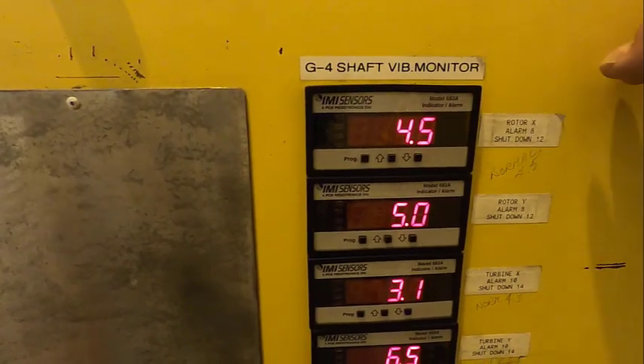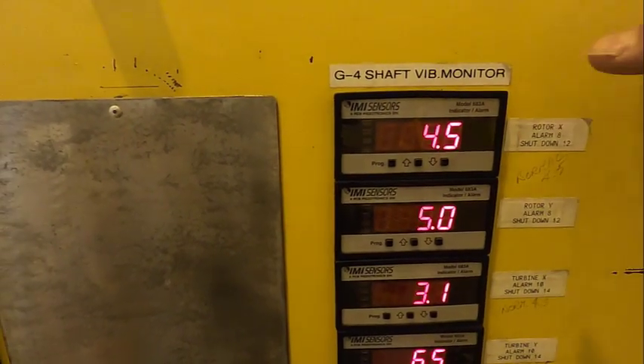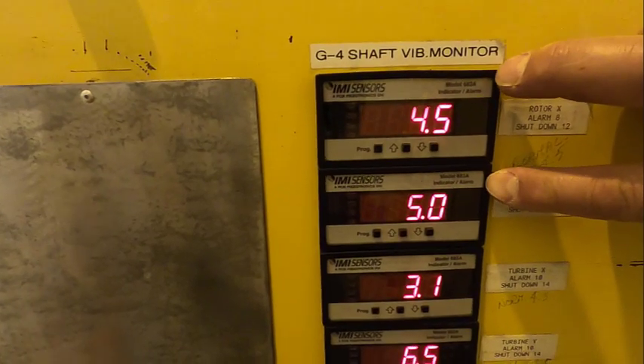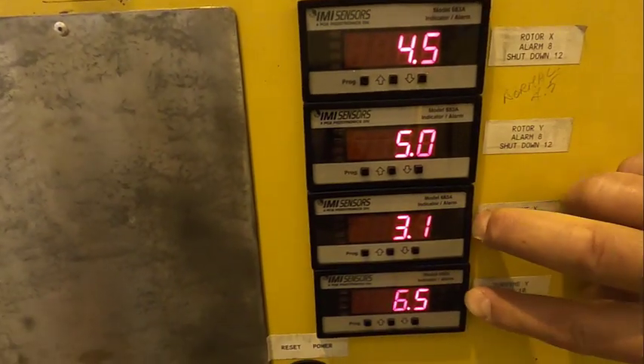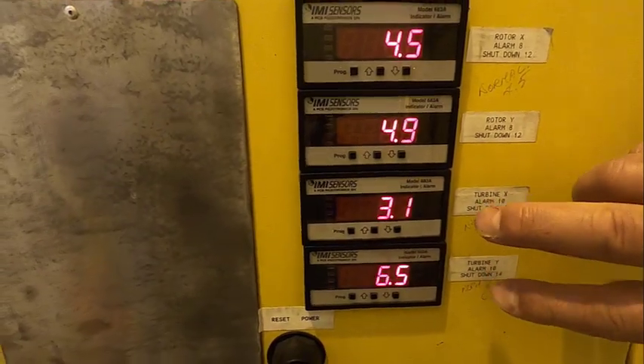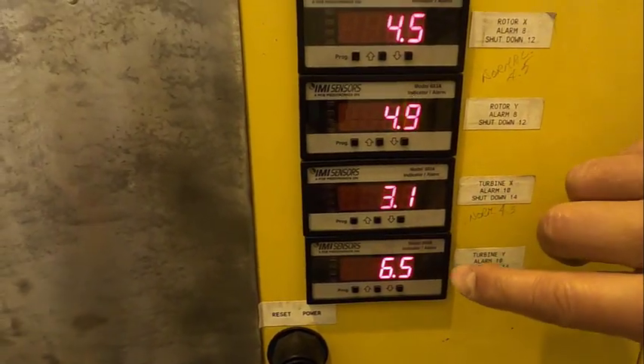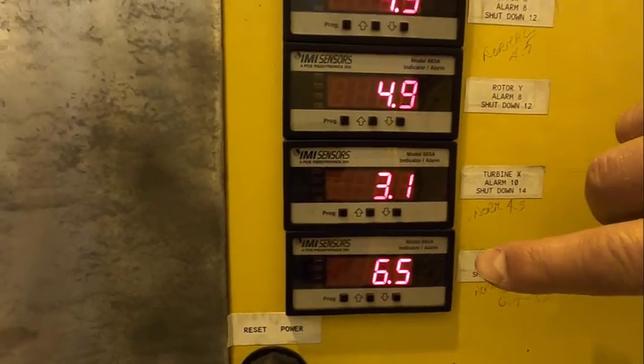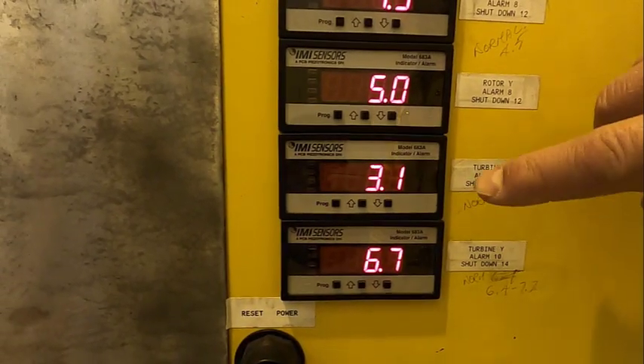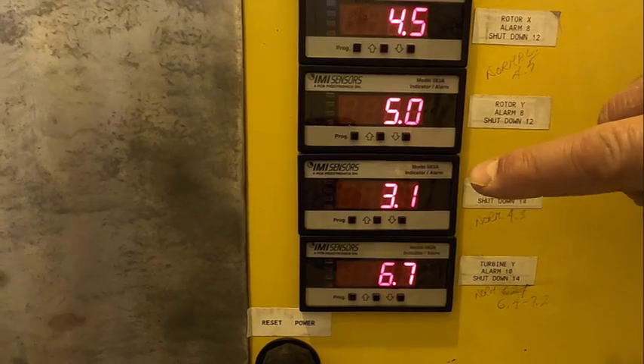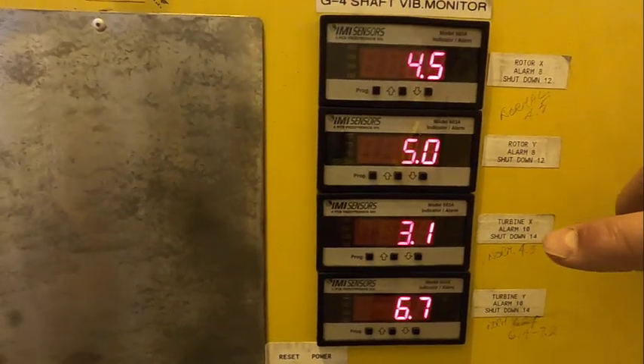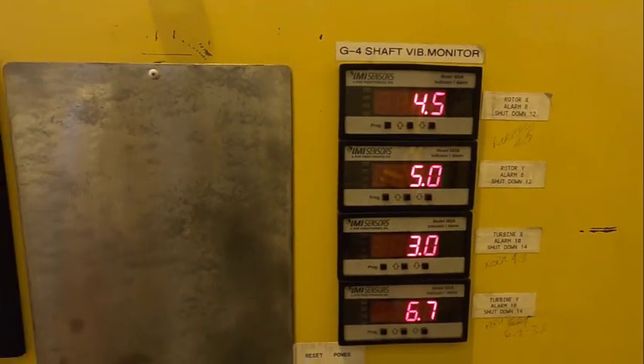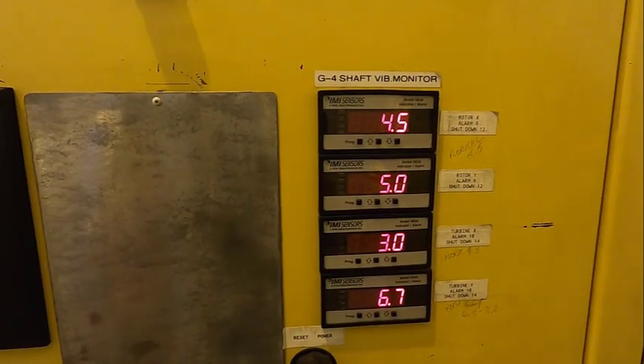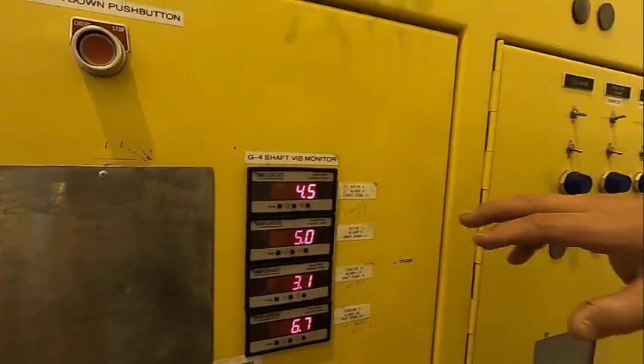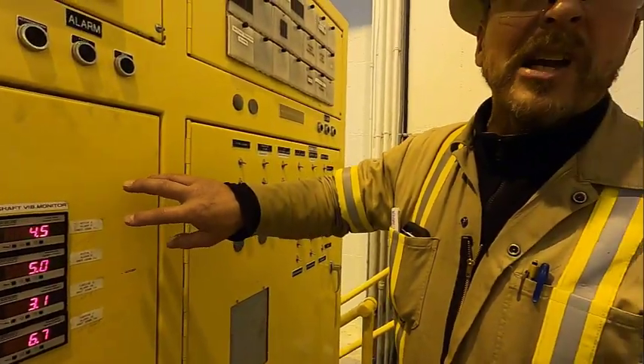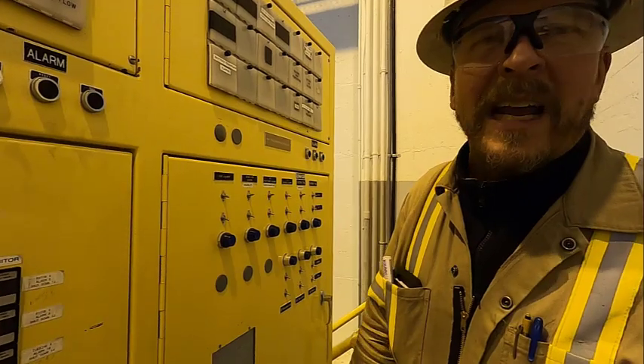This gives us the actual physical run out of the shaft. So these two look at the upper part of the shaft of the generator, and these two look at the shaft at the turbine. Depending on what's going on, if these ones read high, this will actually shut the unit down if it gets a high enough reading. And again, it tells us to do a bearing adjustment, or if there are other issues around that. But it's just a physical monitoring. If something comes loose in the rotor generator, that's another fail-safe check for the unit to make sure it doesn't incur a lot of damage.